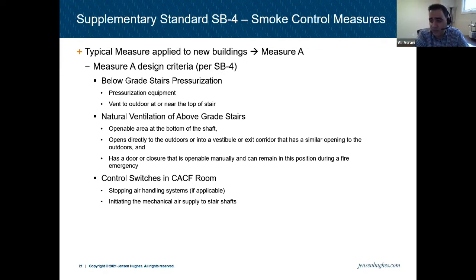So when you have that, there are control switches in the CACF room that we need to have, another requirement based on this measure. So you can stop the air handling system, if applicable, if you have an air handling system serving more than 2 stories, let's say, generally. So you have to have a switch for it, which is pretty common. Again, you see that switch. And you should be able to turn on the fans for pressurized stairs. So if your below grade is pressurized, which is required to be pressurized based on this, you need switches in the CACF room for that. So that's measure A, pretty typical.